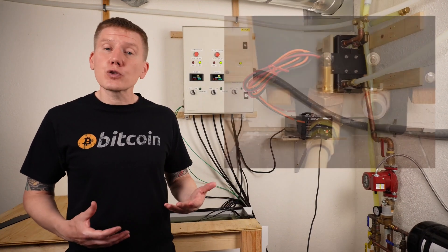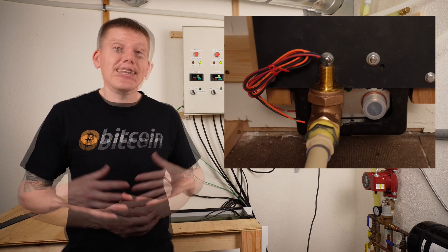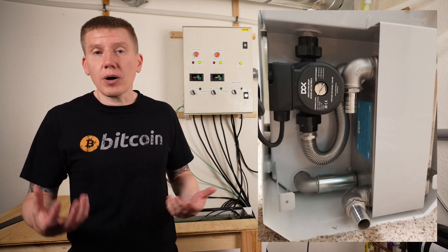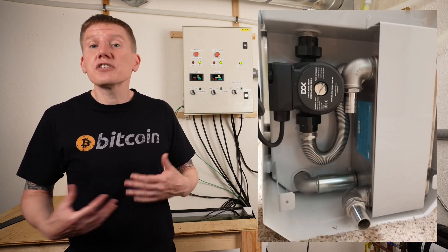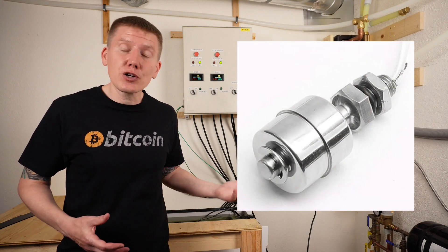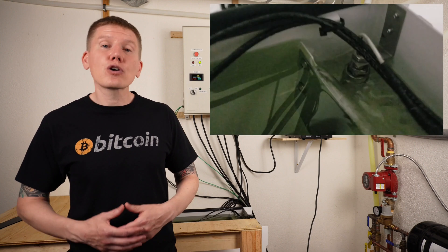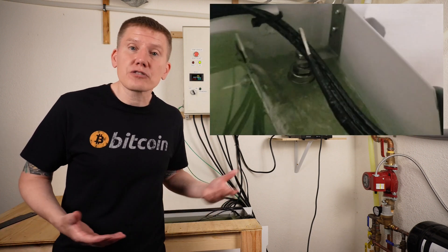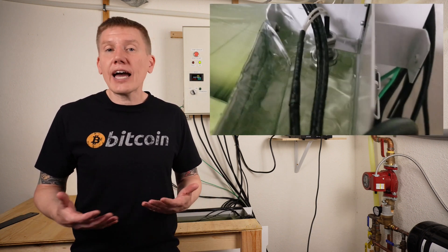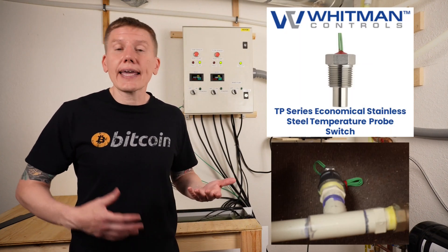Now in my old system, I had a flow switch between the pump and the heat exchanger to detect any type of pump failure or system leak. Now, I can't insert that type of flow switch here. That would mean ripping apart all the lines between the pump and the heat exchanger, and there's just not enough room down there to fit the flow switch in. So instead, I decided to go with a level switch. This switch sits in my hot coolant recovery, and this type of switch is normally used in chlorine pools. This switch is made to handle chlorine environments, so it should handle the dielectric fluid well. I attached the switch to my tank using some sheet metal and some pop rivets I've had from a past project.